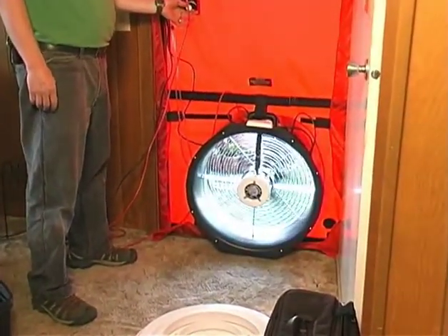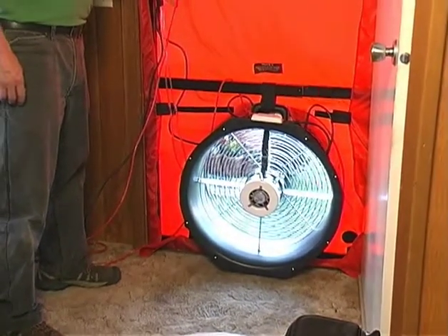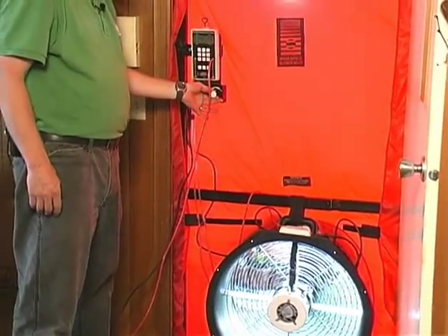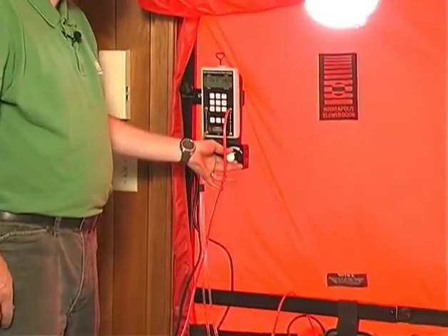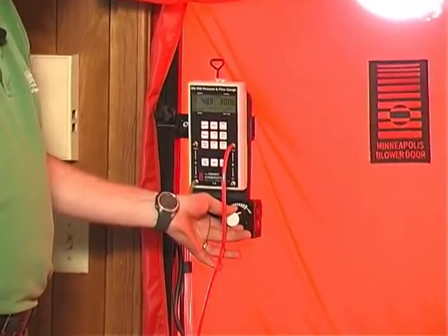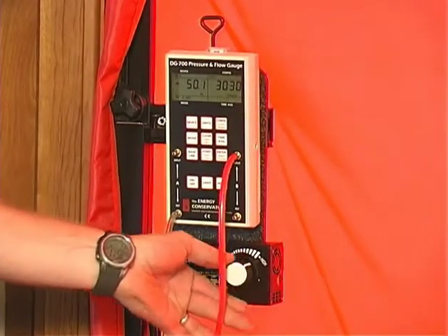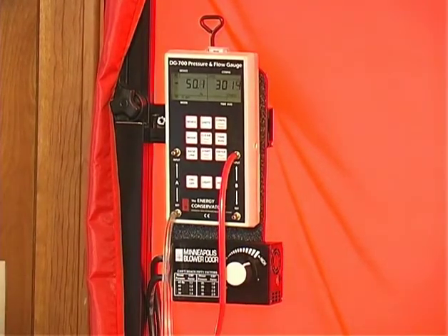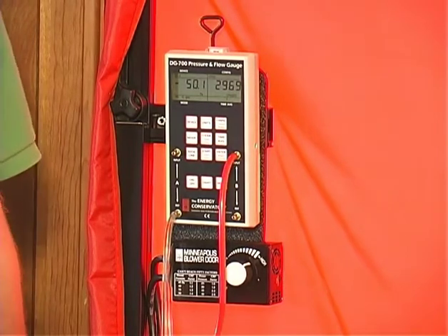I bring it up slowly, and we're working up to 50 pascal pressure difference between inside and outside. We're almost there. A little bit more, all right. Whoops.